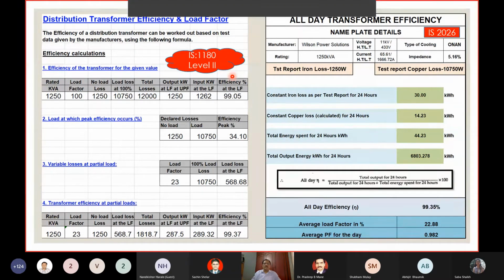Today, no manufacturer can manufacture transformer as per IS 2026 classes. They can only manufacture as per IS 1180 level 2. So this will ensure that only high efficiency transformers will be supplied in the industry. Also, the legislation is working overtime to see if the old transformers can be retired. You must have definitely come across things like old cars, automobiles should be scrapped. Similarly, there will be a policy soon in this country where old transformers, which are 20-25 years old but conforming to IS 2026, will be retired, and new transformers conforming to IS 1180 level 2 or level 3 will become compulsory in this country.